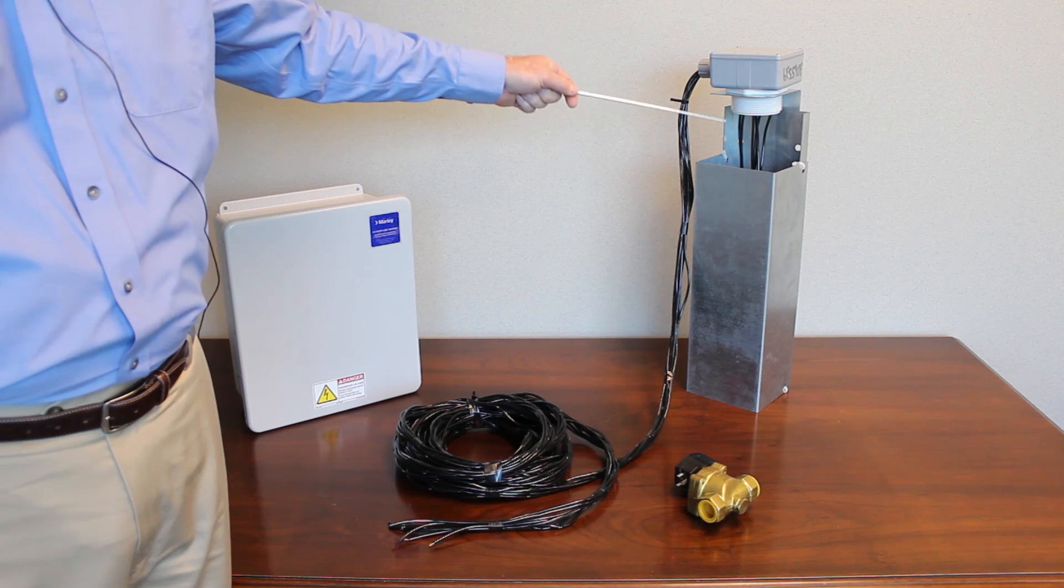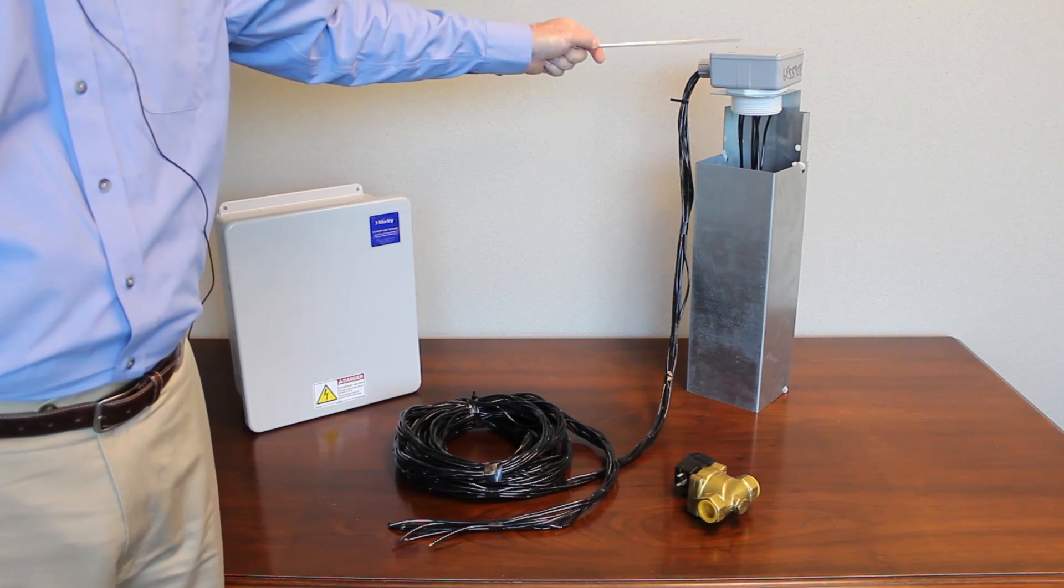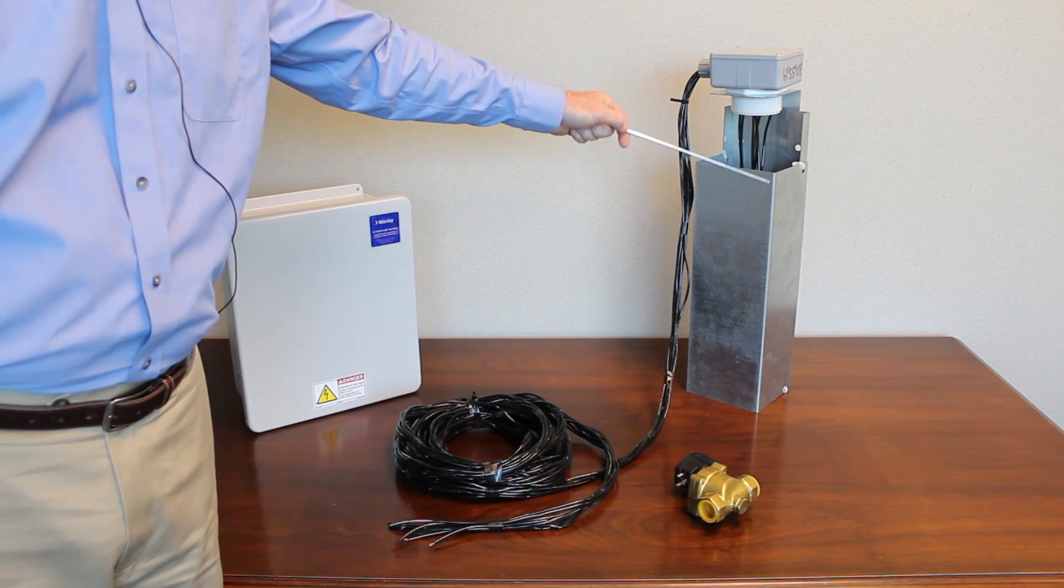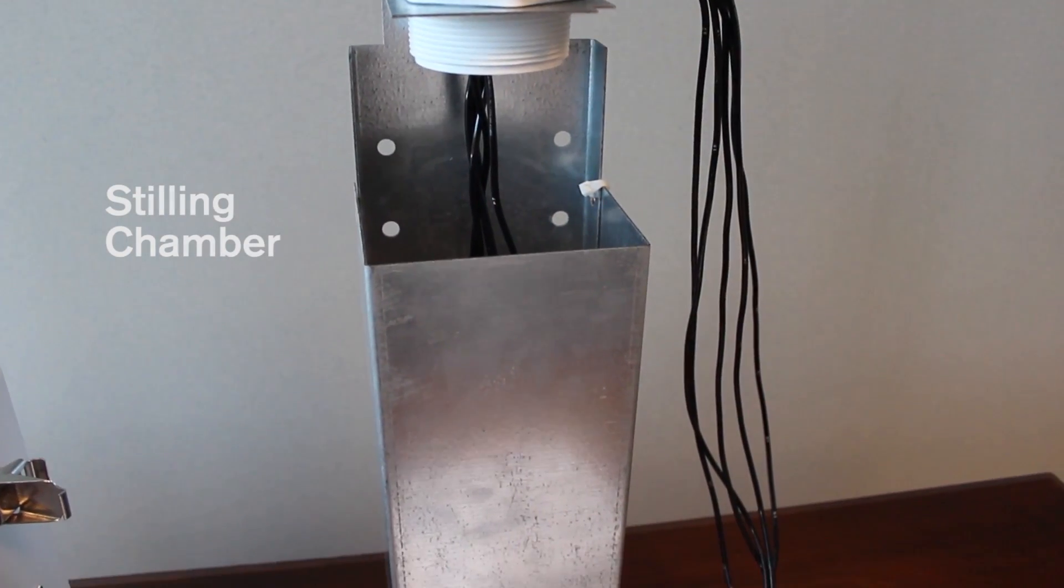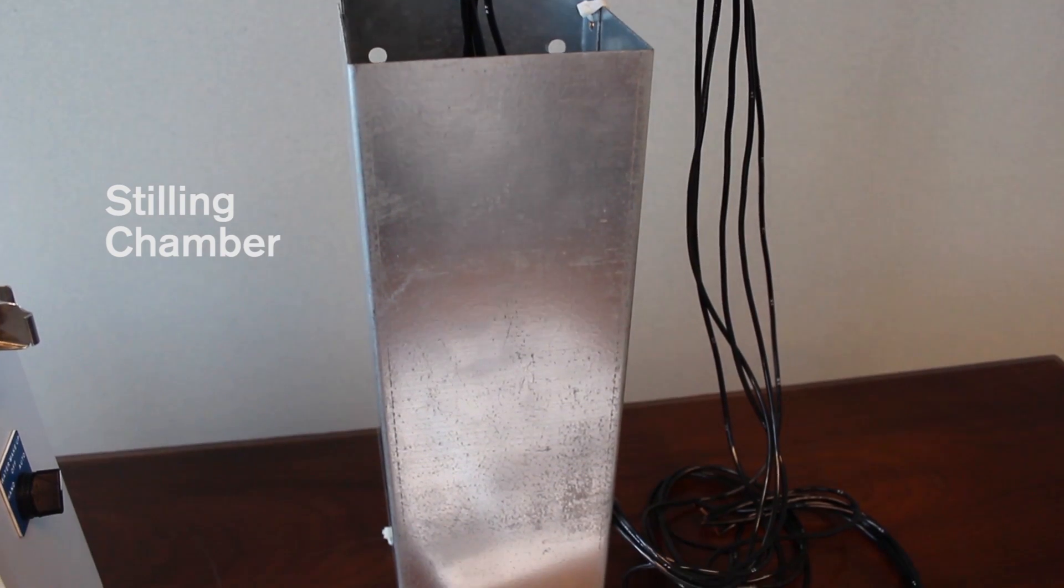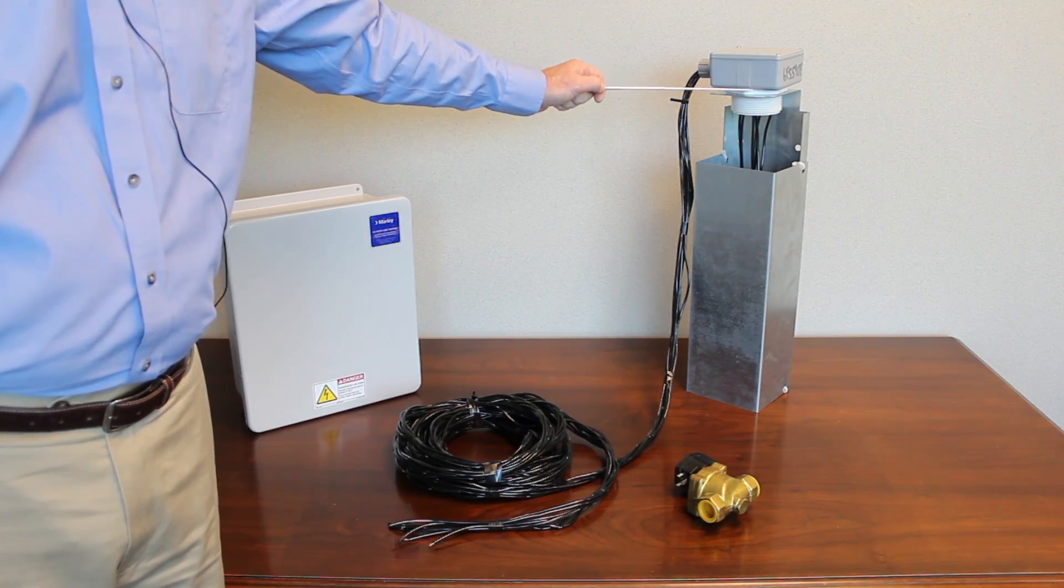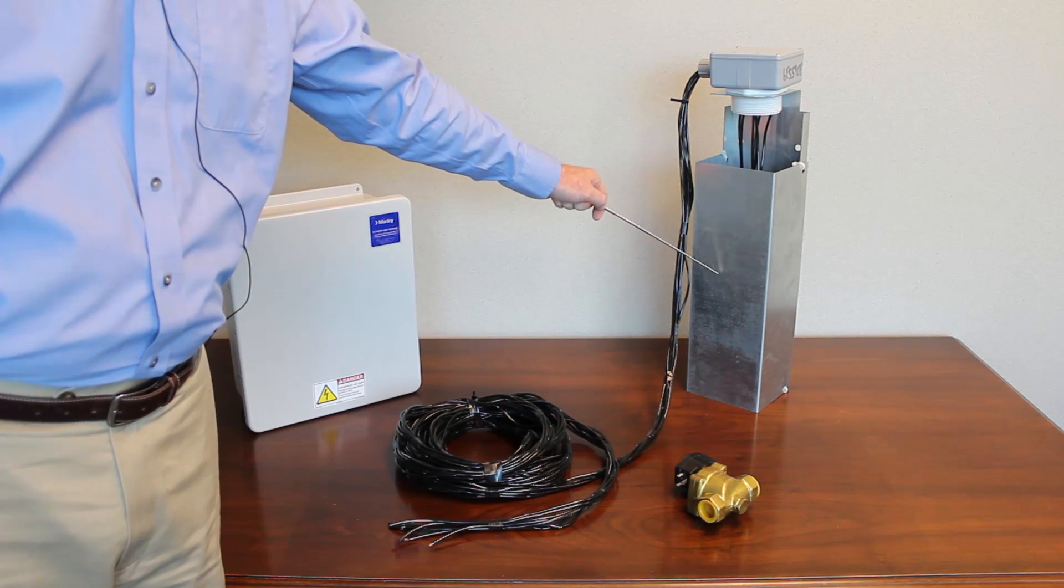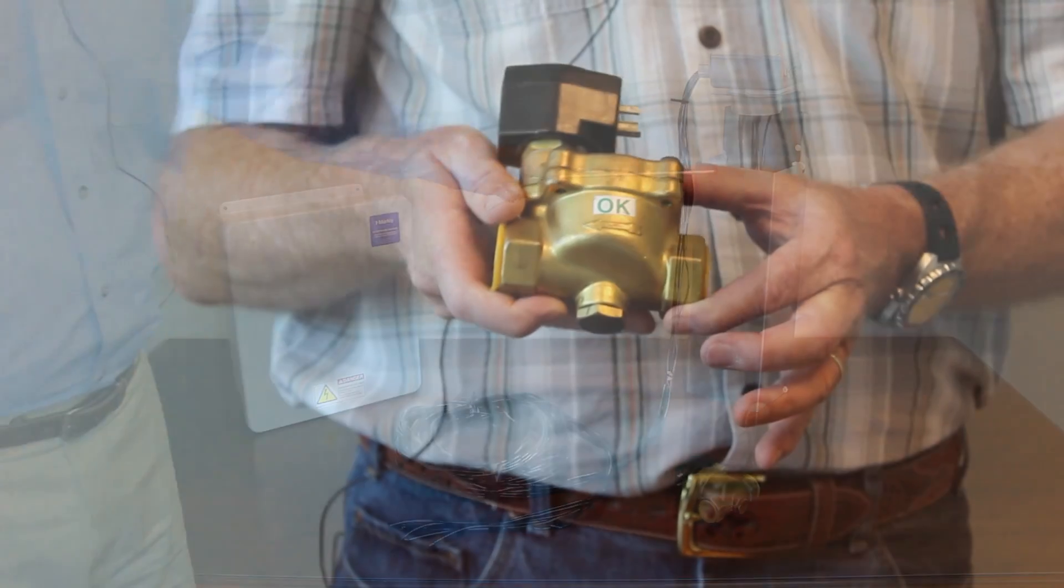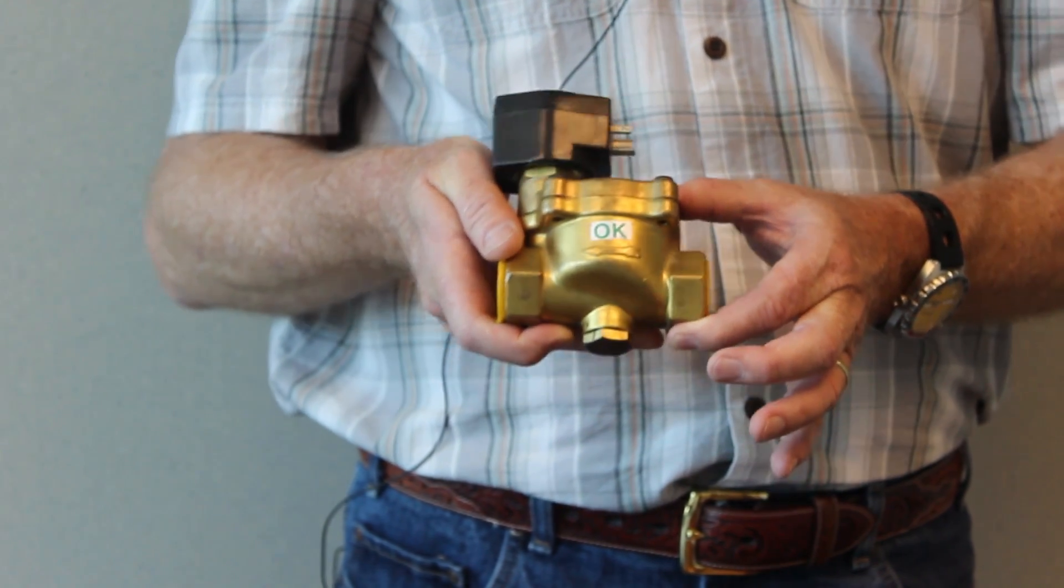The other component is the probe set with a conduit box at the top and the hanging probes coming down to the third component, which is a stilling chamber. The stilling chamber resides in the basin of the cooling tower and its sole purpose is to not only support the probe set but also to calm the water so you get an accurate reading on the probes. And then the final component of the system, if you want makeup, is a makeup solenoid valve.